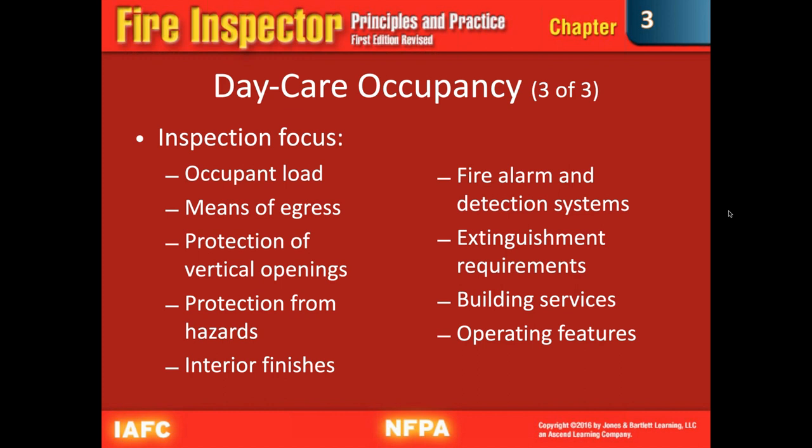The three subclasses of daycare occupancies are distinguished based on the number of clients serviced. So you have daycare occupancies, group daycare, and family daycare. Your inspection focuses on the occupant load, which you're going to see in almost every assembly, every commercial building that has multiple people in it.